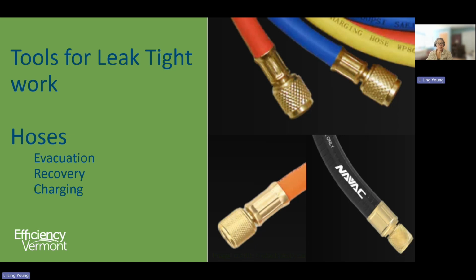So how do you make it easy to do a deep vacuum and proper decay test? A large hose, 3/4 of an inch for a vacuum, remove the Schrader valve, and a communicating digital micron gauge with an app. Most residential systems could reach a deep vacuum in about 2 minutes with that setup, and the app will tell you in a few seconds whether you pass the vacuum decay test. So, large vacuum-rated hoses for evacuation.